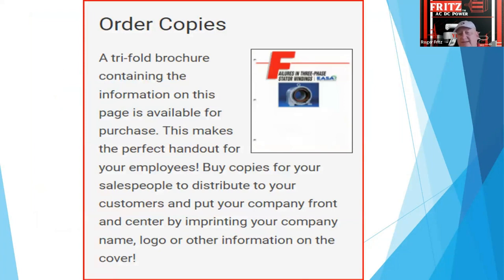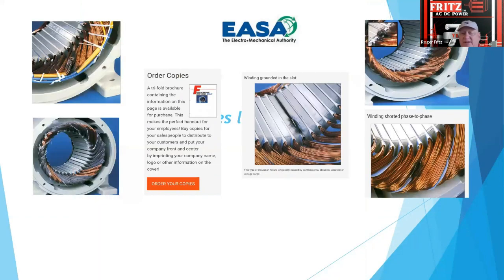You also can go online to easa.com, and you can find this trifold brochure, so that you can literally determine what is happening with the motor. And this gives some examples of when you have spike voltages and stuff, how it shorts or turns the coils out. This happened to be one where the imbalance in power, you can see the voltage was so low on this one phase that it was all picked up by the other two phases, and it literally just smoked the coils out. A lot of times they call it single phasing, but a lot of times it's actually just really bad imbalanced power.